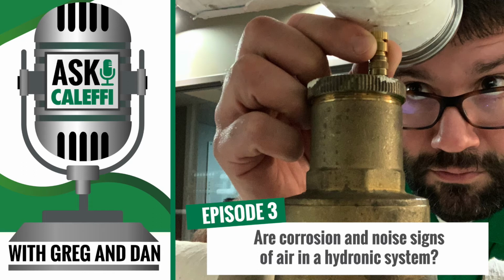Yeah, so having one that's in line in the main loop, a larger one that's dedicated for the entire flow rate of the system, is imperative. Right, right. Typically you'll have that on your hot side of the boiler. You want to have that on the supply side coming out of the boiler and the suction side of the pump. Right. So we want the highest temperature and the lowest pressure. That's going to be the best for removing air out of the system. Right. They'll perform well for you.